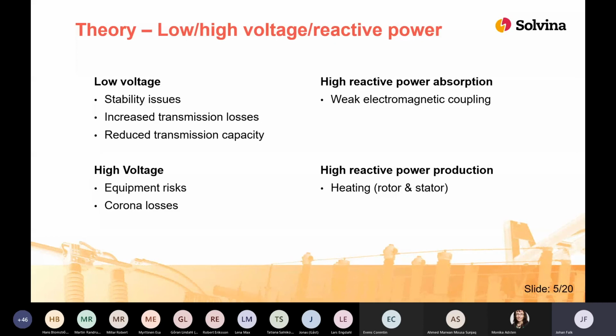Regarding reactive power, we have mainly been focusing on the effects it has on the generators. So if a generator is absorbing a large amount of reactive power, this might weaken the electromagnetic coupling, which has a negative impact on, for example, the fault ride-through capacity. And this might lead to an increased chance of the unit disconnecting during faults. And if a unit is producing a high amount of reactive power, this might cause heating problems.